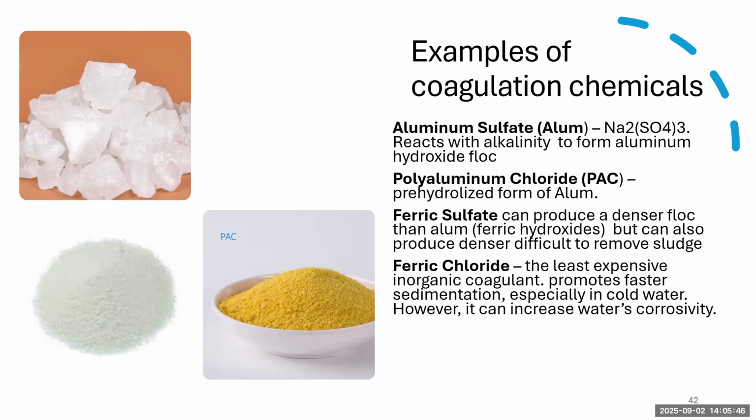It's least expensive because of that reason, and it provides fast sedimentation and dense floc. It works well even in cold weather or cold water. But one of its main drawbacks is its corrosivity, and it can increase the corrosivity of water.